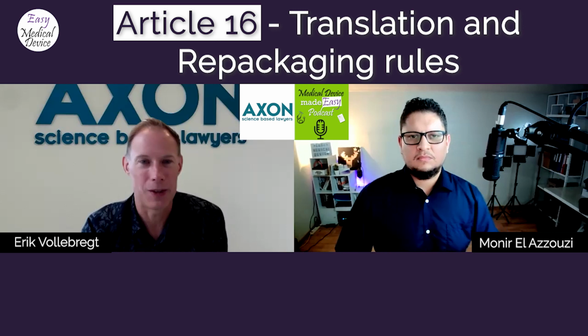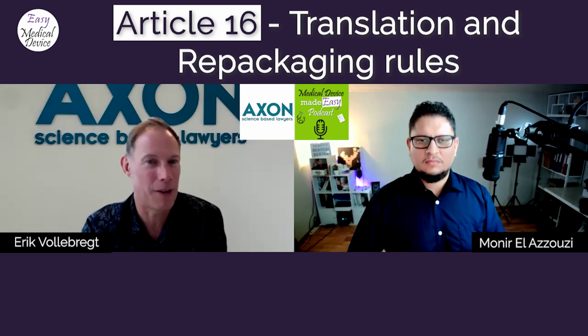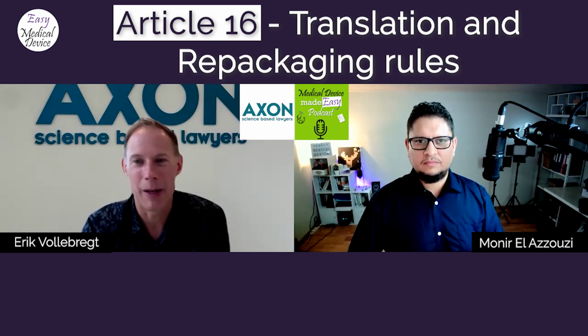Also, I think if you look at translation processes at manufacturers in scope of Annex 9 in production, then your translation is actually also a quality controlled activity. And if you have a shitty translation consistency process, then a notified body will write you up for it. And I've actually had cases on my desk where a parallel importer had really badly translated the original IFU, instructing users to do things that were actually pretty dangerous, to leave the device in place a lot longer than you actually should, with potential big chance of infections. Yeah. So it's not like they are making this up for fun.